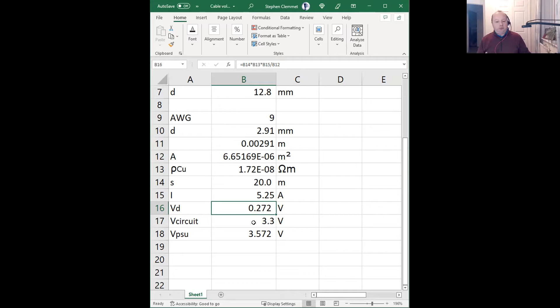This is the resistivity of copper, which is given to us. Then we've got our cable length, which we've got as 20 meters, and then how much current we're going to shove down it. That'll easily tell us the voltage drop. So if we had a circuit running on 3.3 volts, and we were 20 meters away, we'd need our power supply to actually be at 3.57 volts in order to accommodate the voltage drop in the cable.